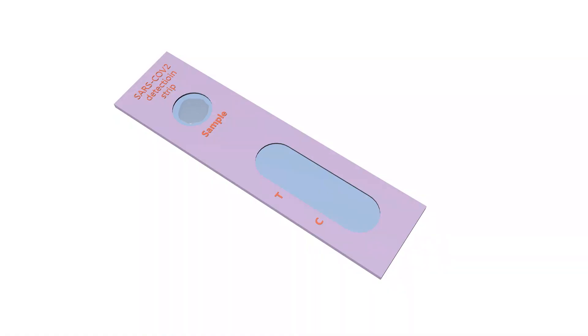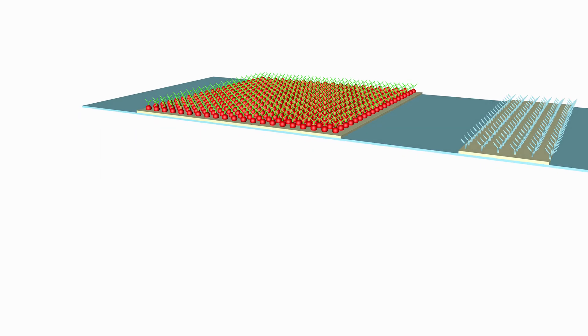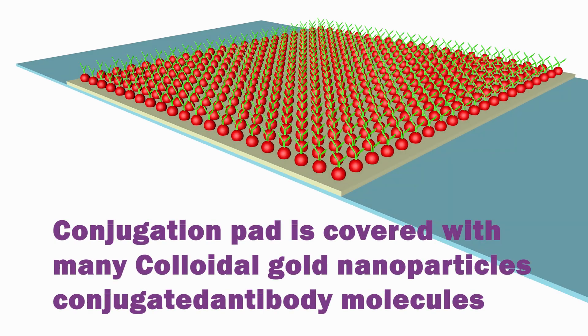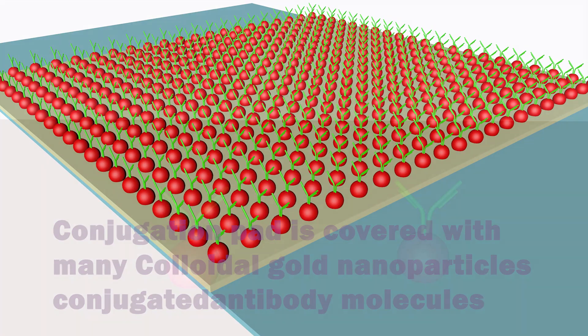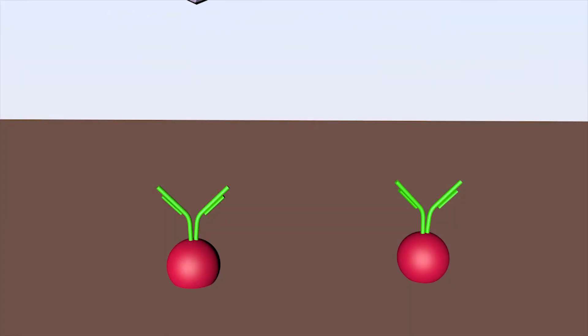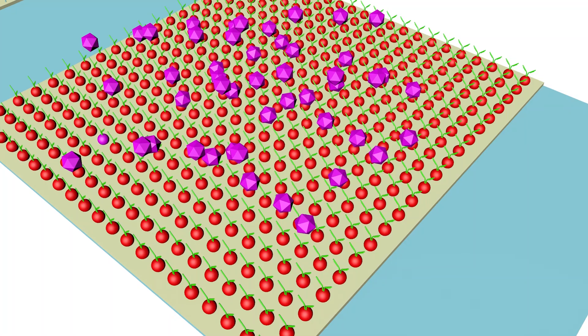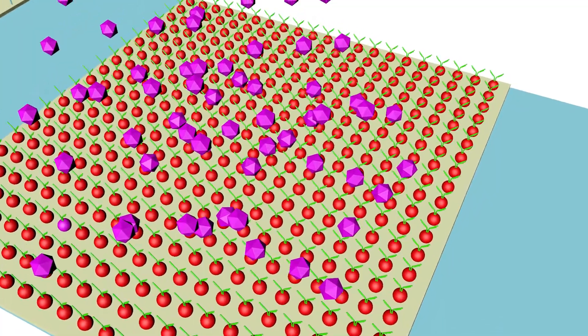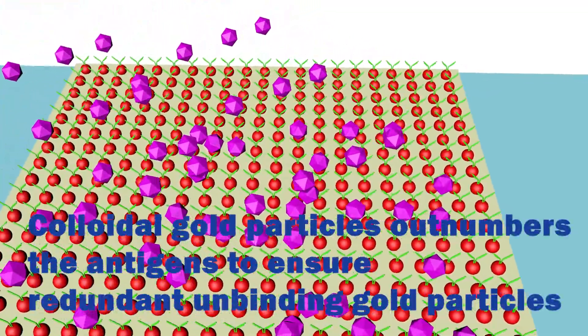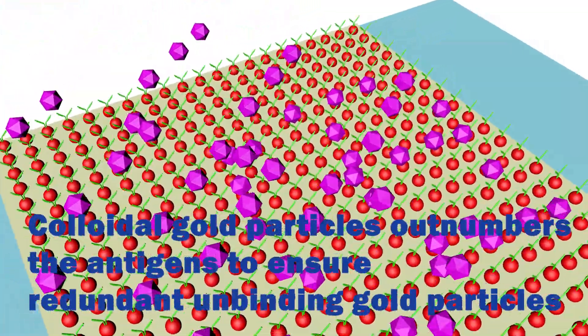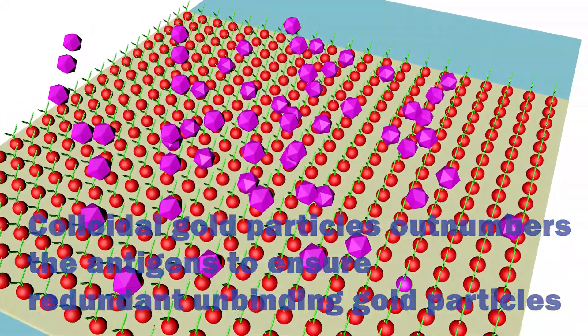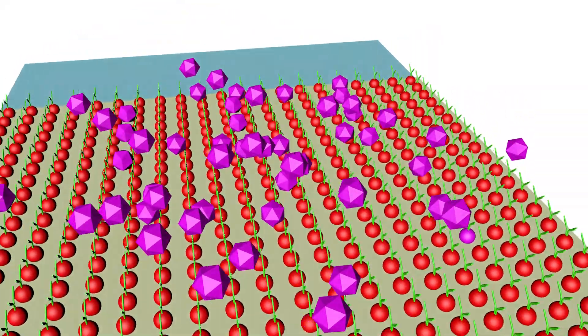The sample liquid arrives first at the conjugation pad. This pad is covered with a large number of colloidal gold particles conjugated with antibody molecules. These antibody molecules recognize and bind to the coronavirus antigens. It is important to note that the colloidal gold particles must outnumber the coronavirus antigens so that there are always redundant colloidal gold particles not bound to the antigens.